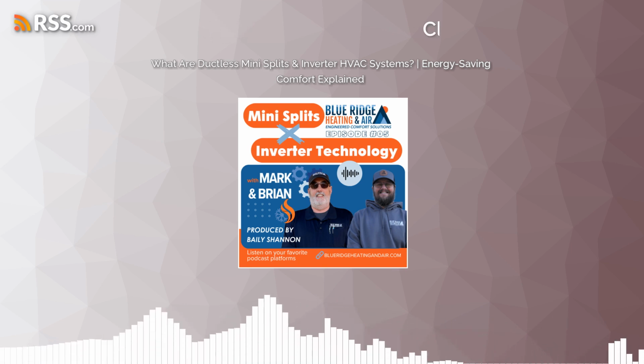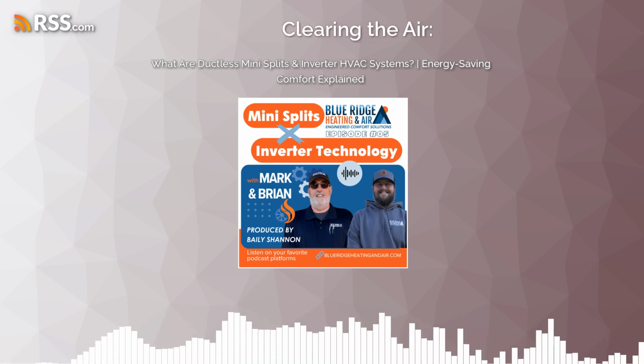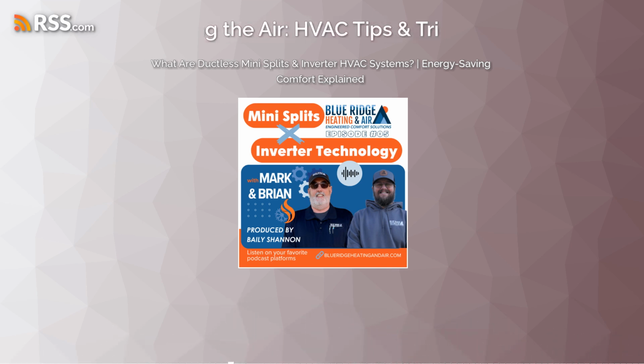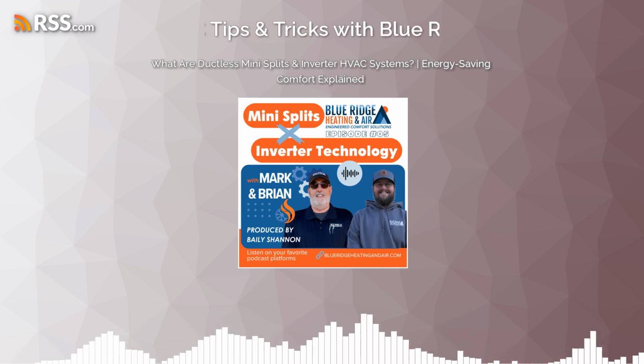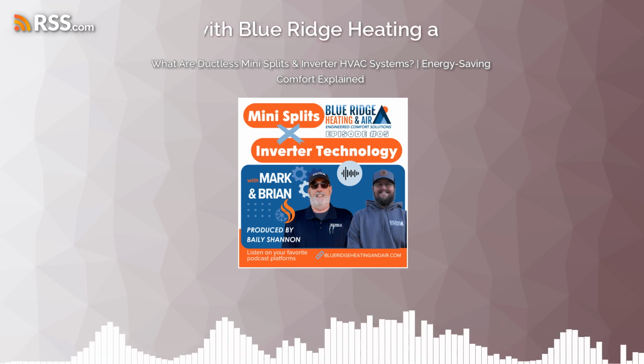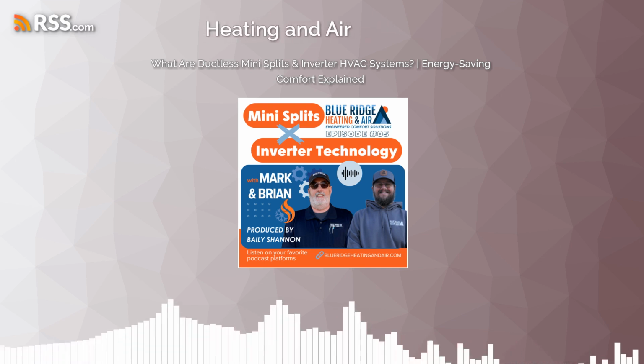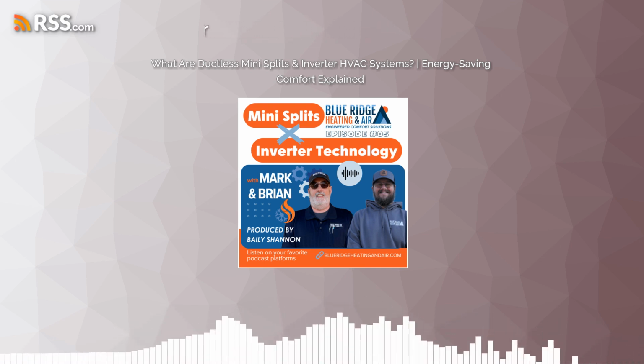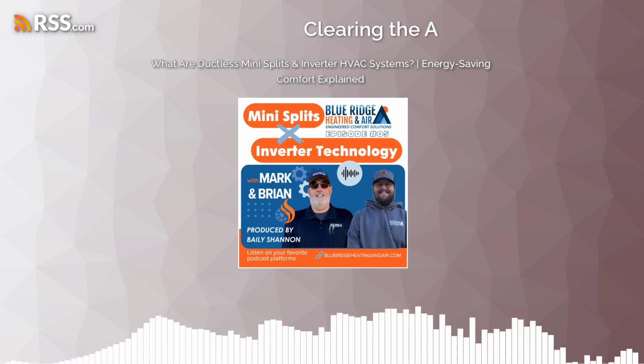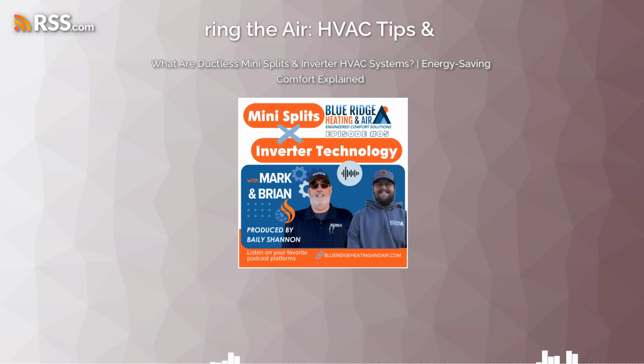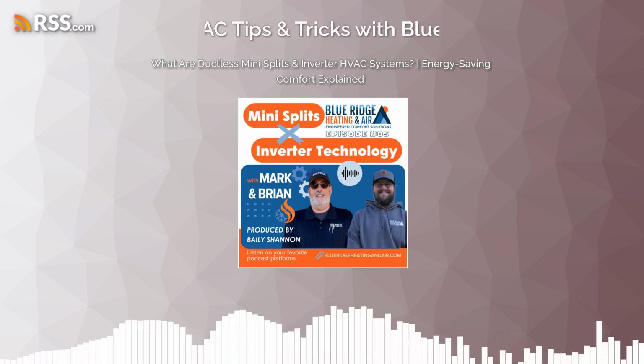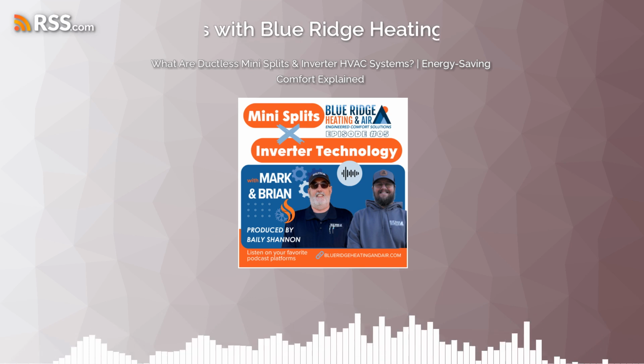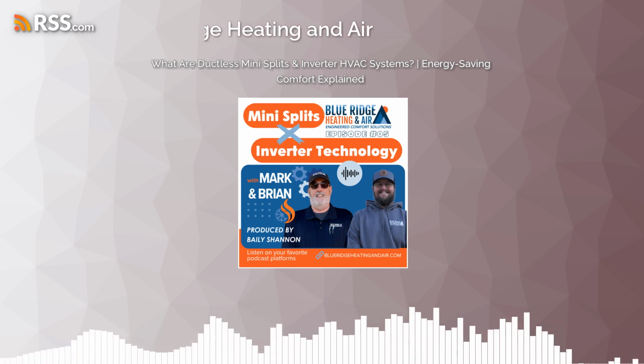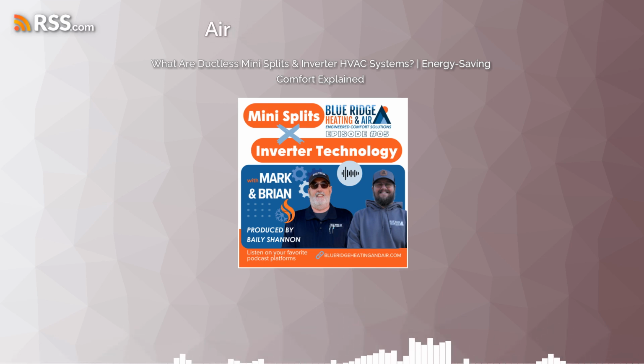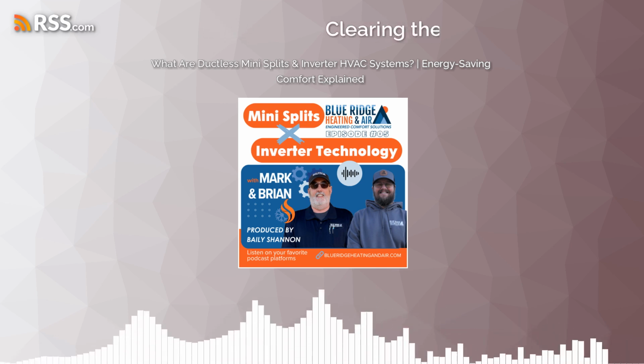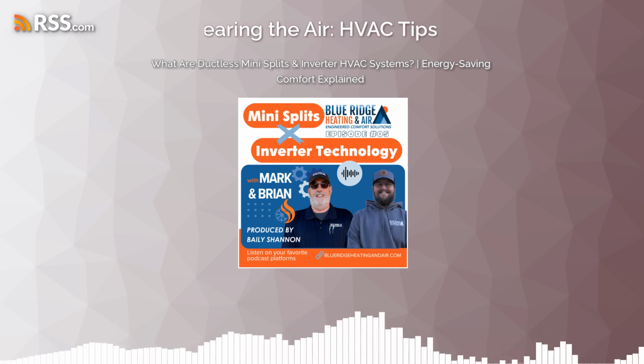Now with Mitsubishi and Daikin, there's also cold climate or hyperheat products you can purchase. Can you tell us a little about what hyperheat is? It's pretty awesome, actually. Conventional heat pumps can heat comfortably down to about 30 to 35 degrees. Newer technology can go down to maybe 25, but after that it's relying on another source of heat to assist the heat pump.